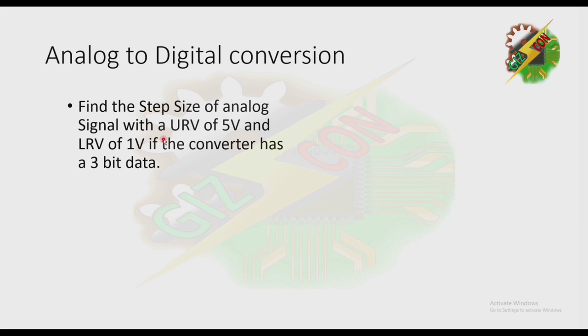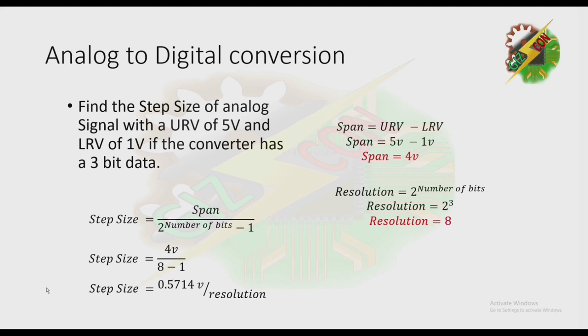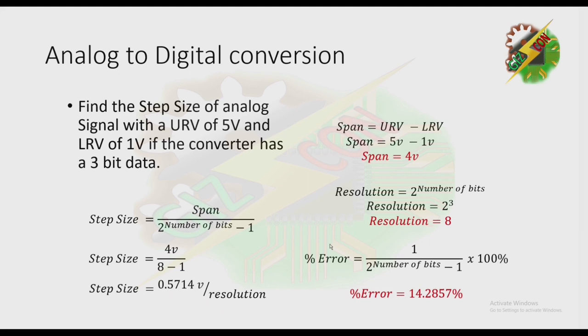Let's have this exercise: find the step size of an analog signal with a URV of 5 volts and LRV of 1 volt, if the converter has 3-bit data. To find the step size, we use the formula: Span over 2 raised to the number of bits minus 1. First we solve for the span, then the resolution. We get a step size of 0.5714 volts per resolution. The percent error is 1 over 2 raised to the number of bits minus 1, times 100%, which gives us 14% error.